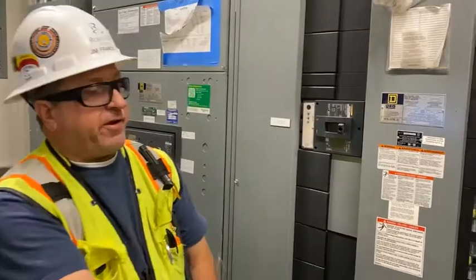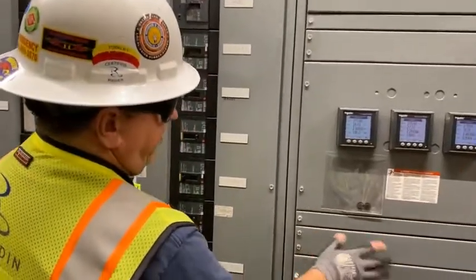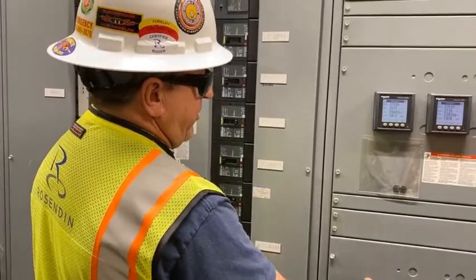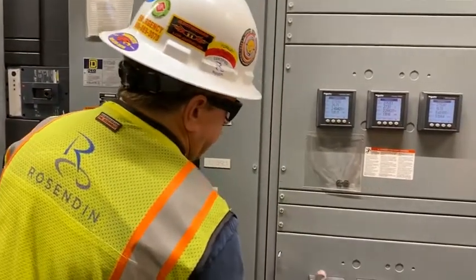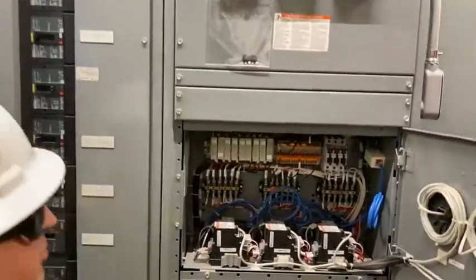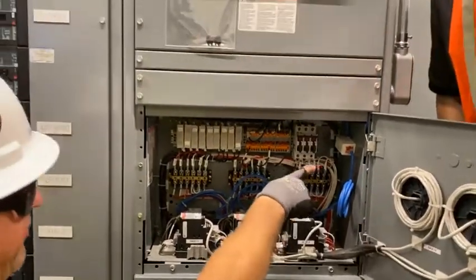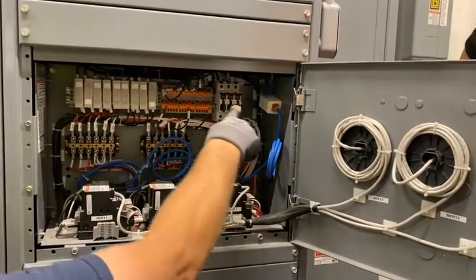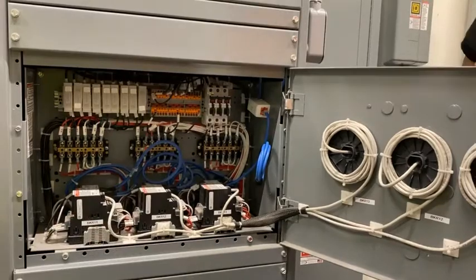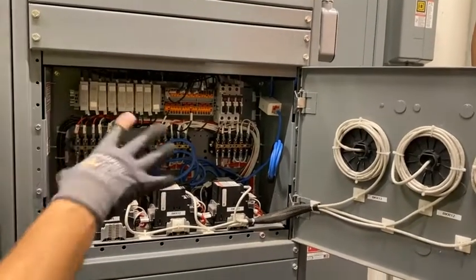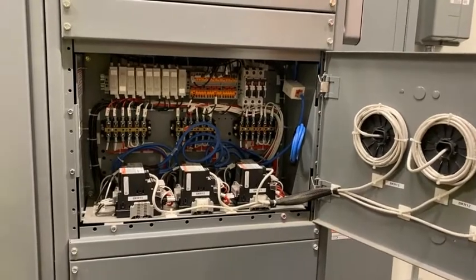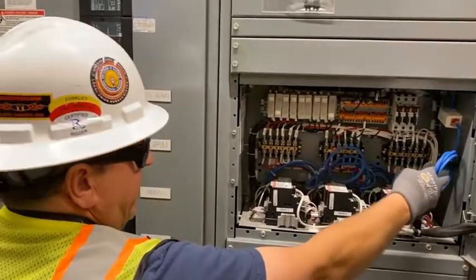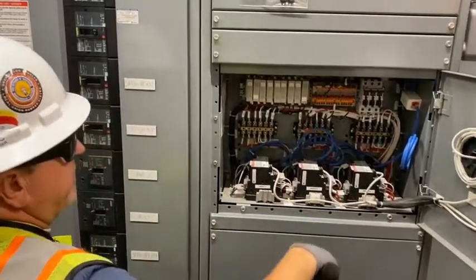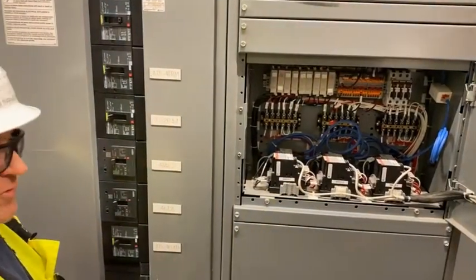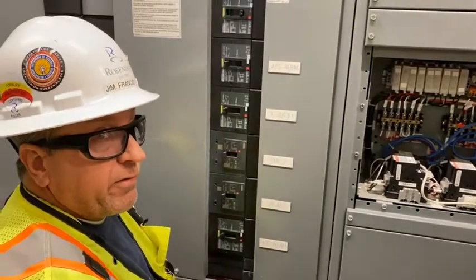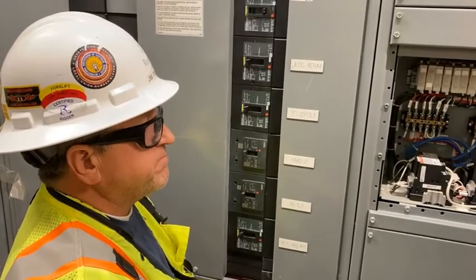If you were to open this up, it's pretty much isolated. There's no bus bar in there. Well, I can show you. So there is 480 in here, but these 3 meters here are fed, and if you needed to isolate them or turn them off, there are 3 little breakers in here that feed those, in each little bucket here. And you see the data line, which is daisy chained from bucket to bucket. Then it goes back to the BDF room, so they can pull it up on the network and see the power being used.